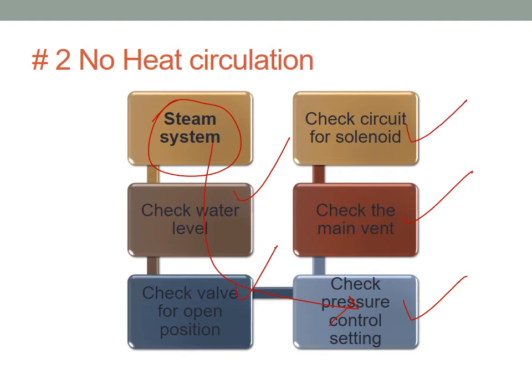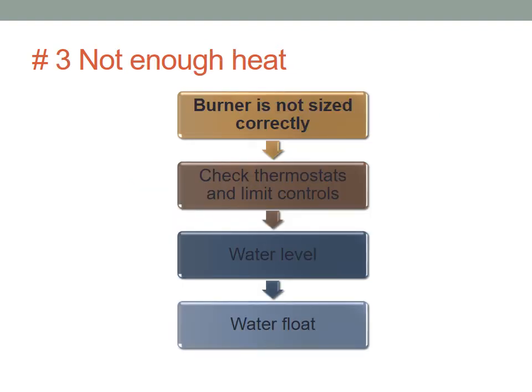Check the circuit for solenoids. Maybe there are some solenoids that open and close the steam. Not usually, but if there is a solenoid, check it and make sure it's working. If we don't have enough heat, in any system, this could be that the burner is not sized correctly. Boiler, furnace is not sized correctly. It could be undersized. If this has always been the problem, it could be a design problem.